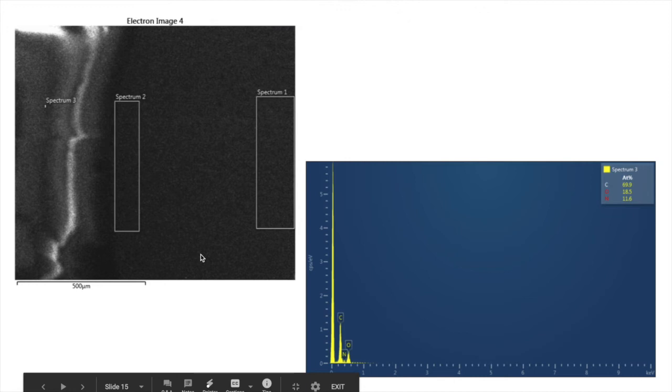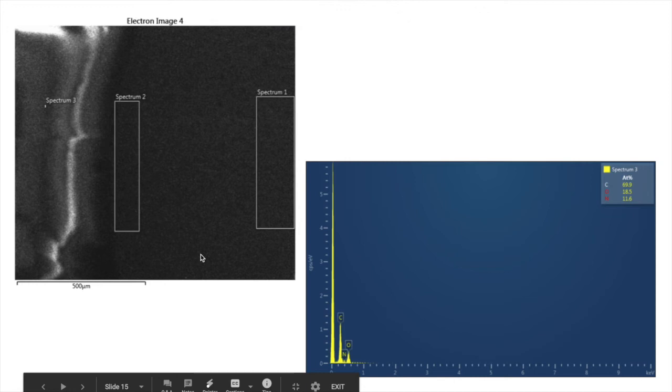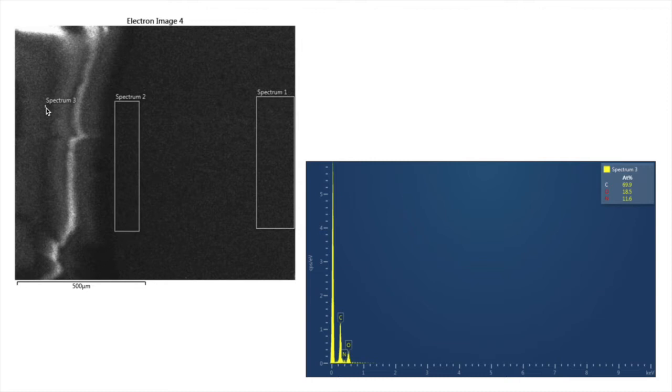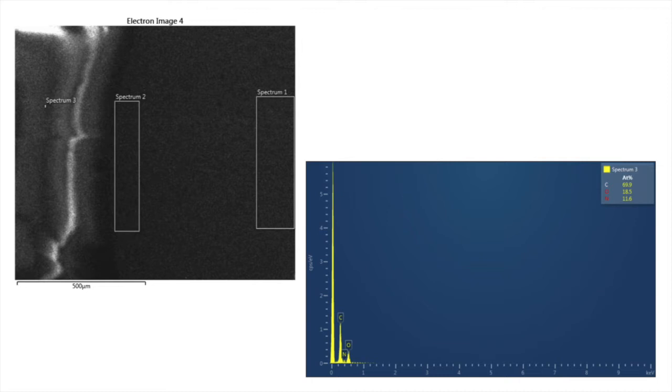This up here in the left corner is an SEM image in an SEM that has an EDS. And so there's also spectrums denoted. Spectrum three, which is just a tiny little dot, that is an example of a point scan or that stationary mode. So the beam is held at that one spot and then data is collected. The x-rays go to the detector and they're sorted out by energy.